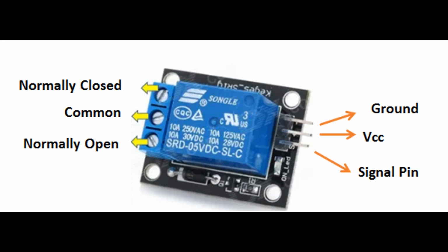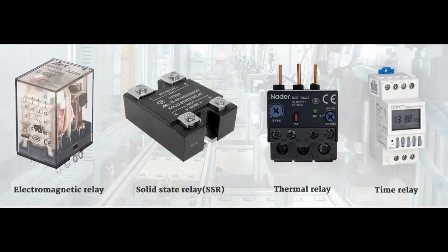Adjustability. Many self-heated thermal relays allow for adjustment of the trip current or temperature setting. This adjustment is typically done using a dial or screw on the relay housing, allowing users to set the relay to trip at a specific current level corresponding to the desired overload protection. Reset. Once the overload condition is cleared and the heating element cools down, the relay resets automatically. Some relays may include a manual reset button or lever for resetting the relay after a trip.